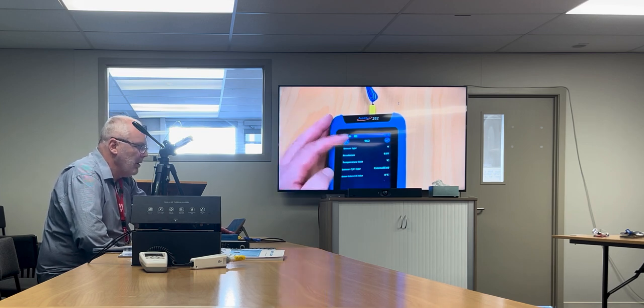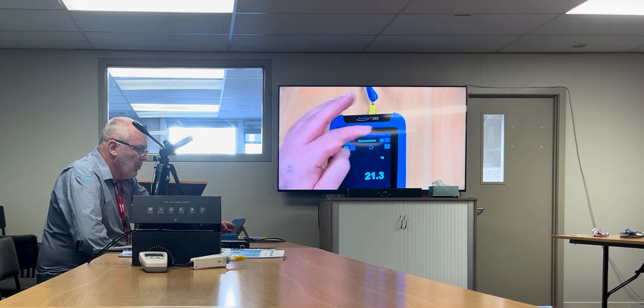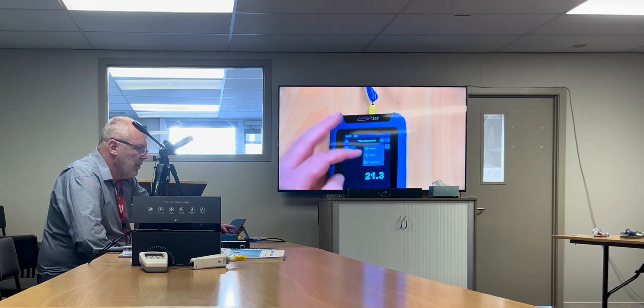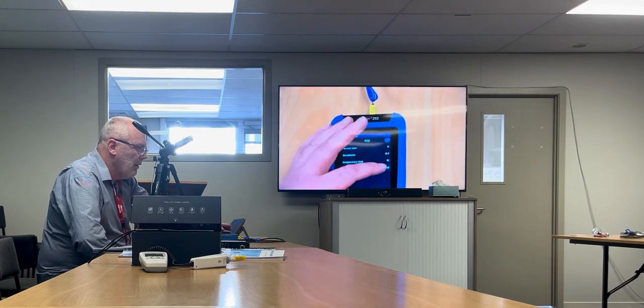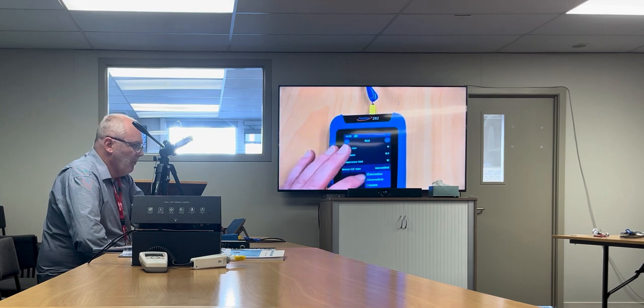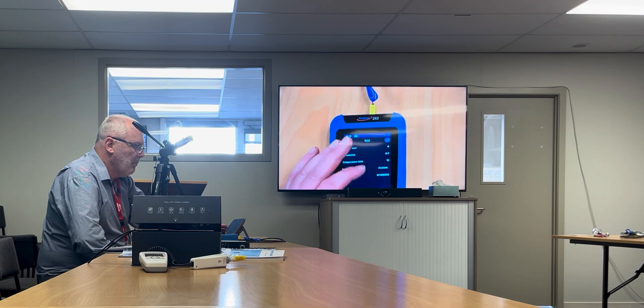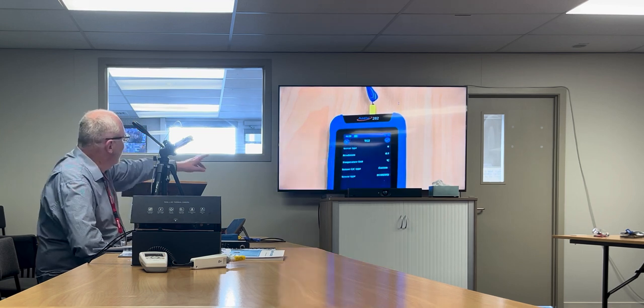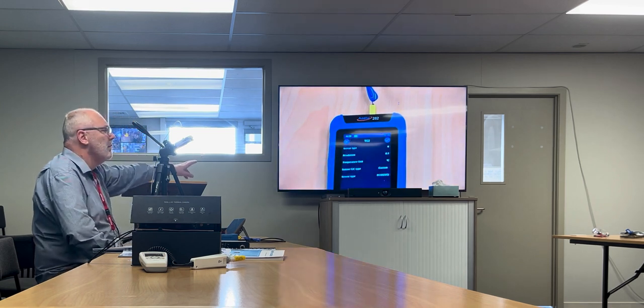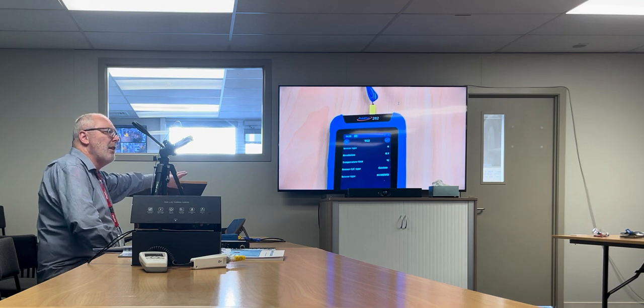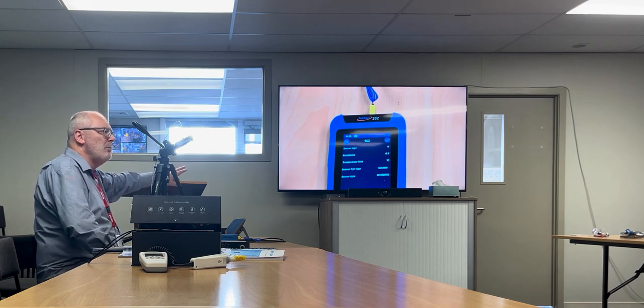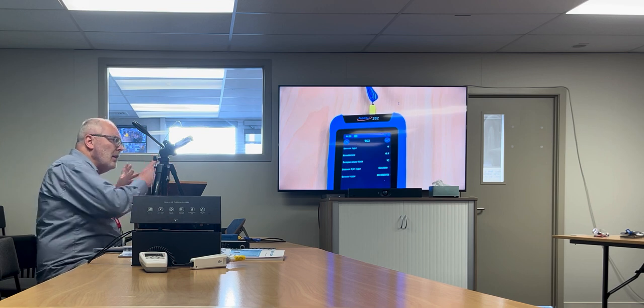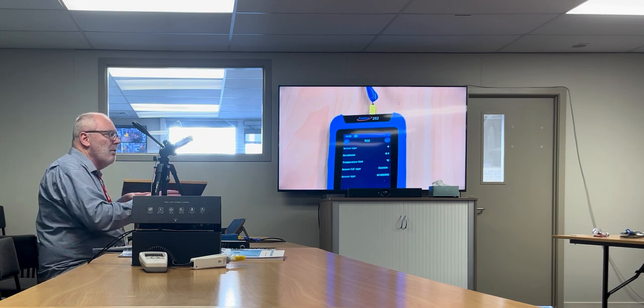So you put in that temperature. What I would call external is what they call custom. So we could go to custom. At the moment it's set to a standard PT100 385. You know that term, PT100 385? 0.385 ohms per degree it increases. PT100 is zero at 100 ohms at zero.